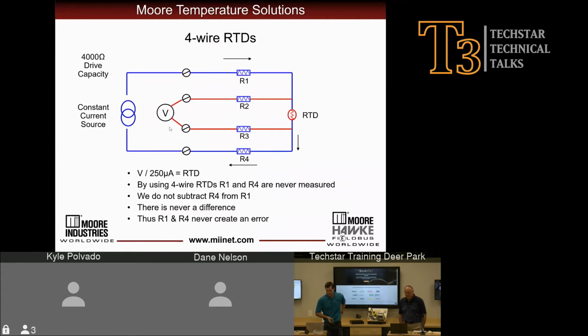Okay. So the 3-wire RTD is a fairly accurate temperature measurement, but it's not the most accurate. There is a way that we can eliminate that lead wire leg from the equation entirely and not have to guess at that other lead wire leg. And that's by using a 4-wire RTD. A 4-wire RTD has 4 leads now instead of 3. And you can see that the 2 high impedance leads right here are only measuring the resistance in the RTD when we pass the constant current source across it. So we're no longer taking the resistance in lead wire leg R1 or R4. Those are both eliminated from the equation entirely. That's why a 4-wire RTD is our most accurate and does not have any lead wire compensation errors that a 3-wire or 2-wire RTD do have.